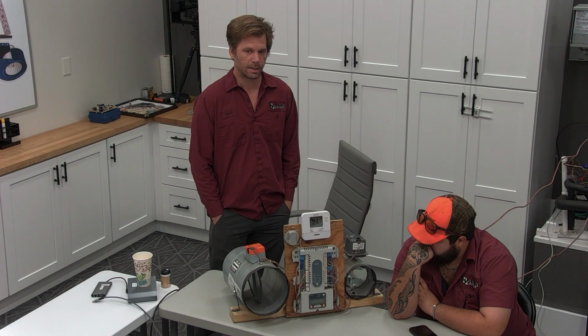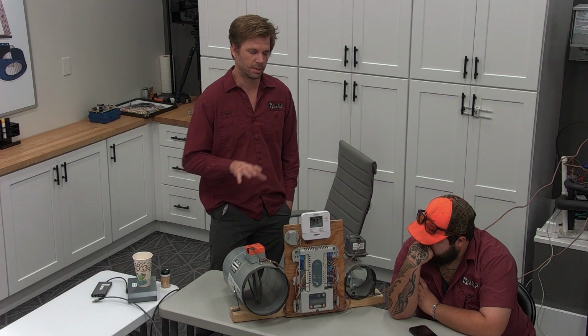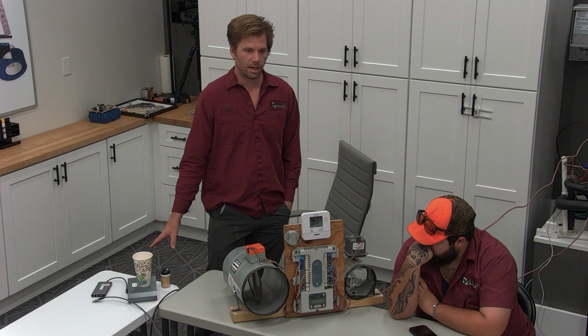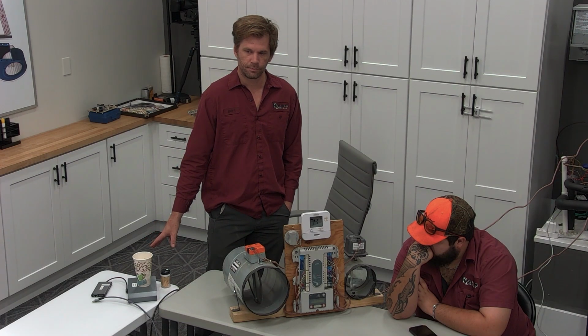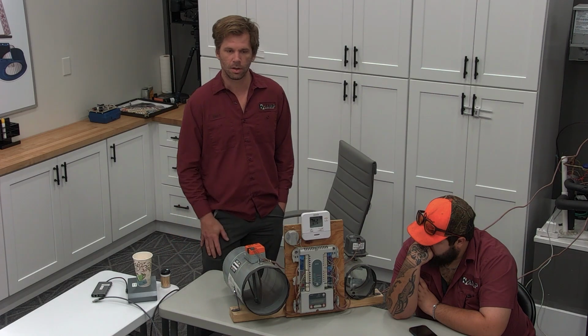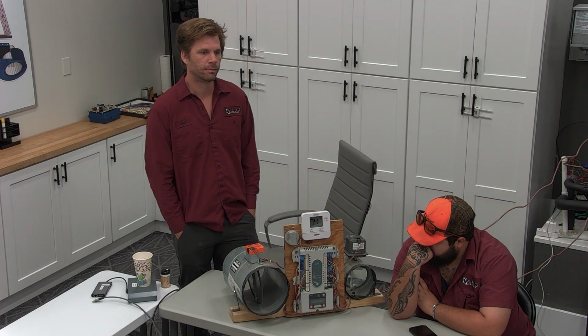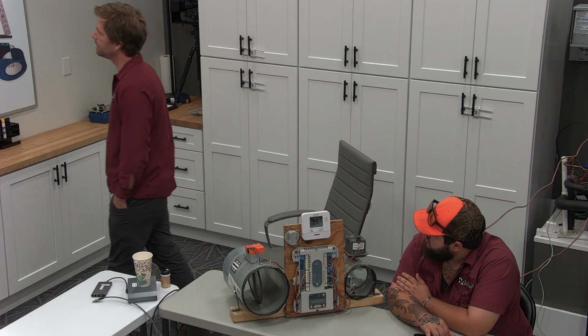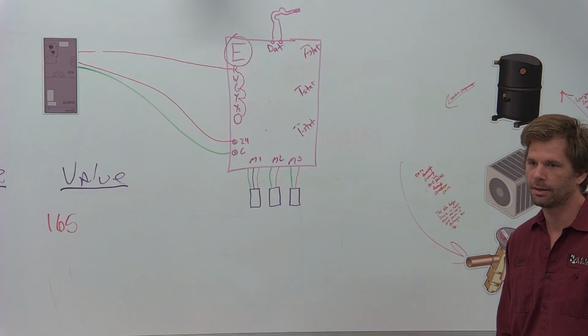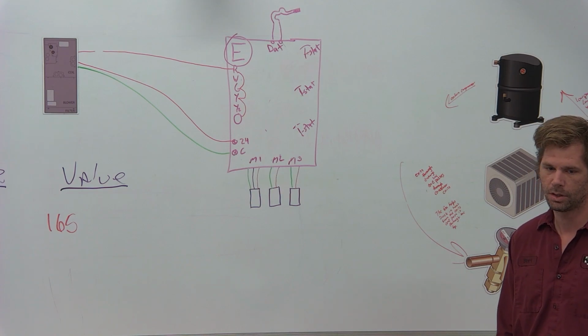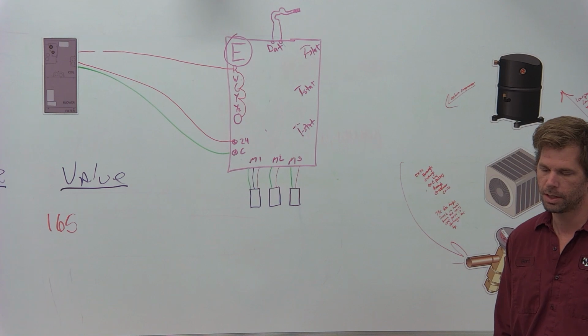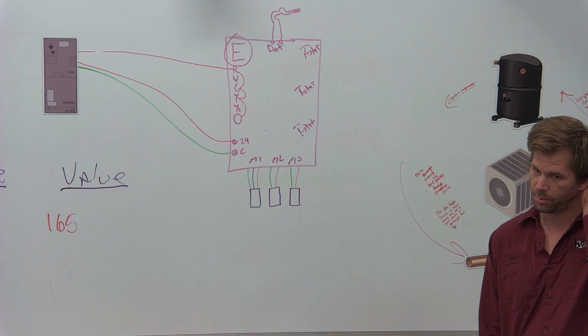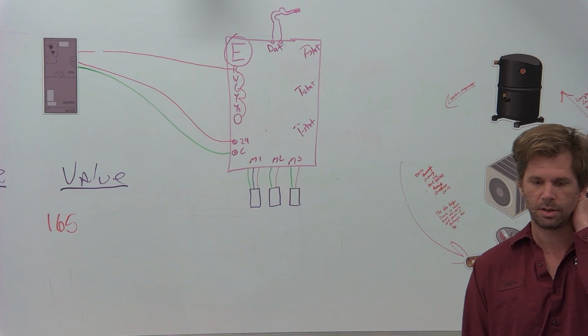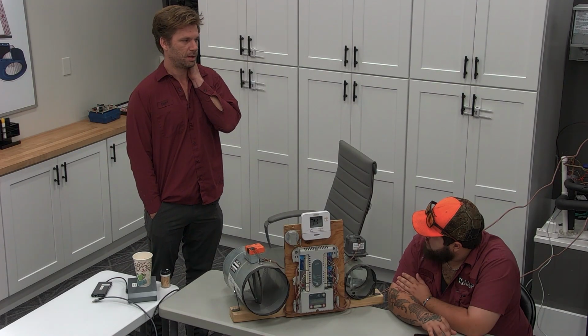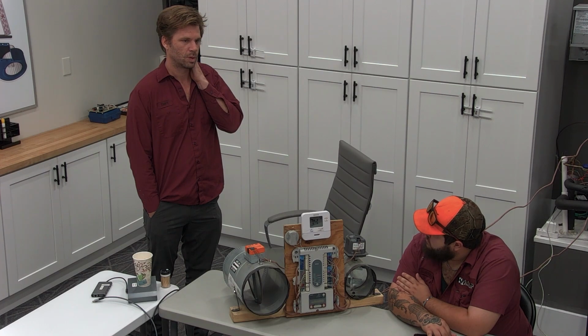So last year there were a couple of scenarios where we had a damper system connected to the AC and furnace setup, and then we had set up the damper panel wrong and we were calling the condenser with our furnace. That's great. DAT sensors, you guys are all pretty familiar with those. To test them, you can look up a 10K chart on Google, test your DAT sensors. And you can also unplug the DAT sensor. I don't want to see anybody quoting a DAT sensor and walking away from a system and leaving it inoperable, right? Unplug it, test the system, leave it running.